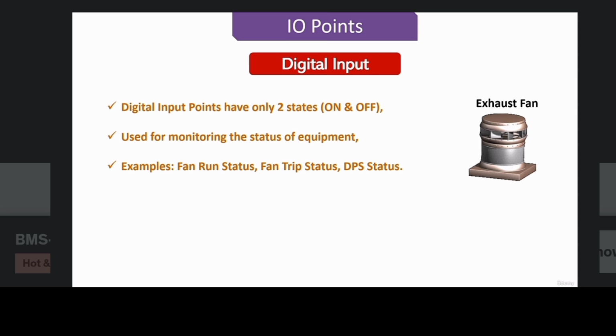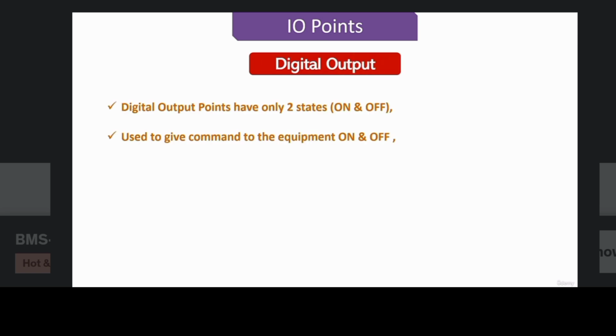These are all examples of digital input points, which only represent that either this equipment is on or it is off. Then we have digital output points. They also have two states and are used to give commands to the equipment, like an on command and an off command. Examples of digital outputs are fan run command, pump run command, and open command for a digital damper actuator. So digital outputs are used to control the equipment and field devices, and they can control only two states. They can either turn it on or they can turn it off.